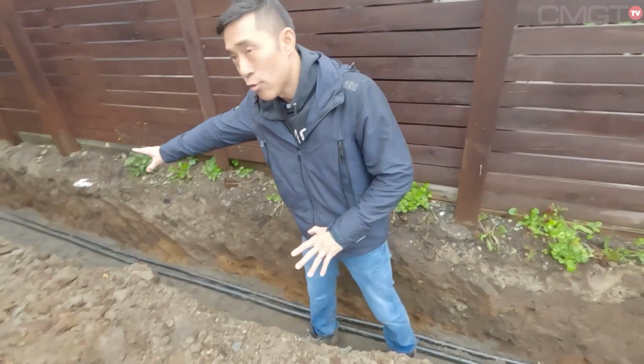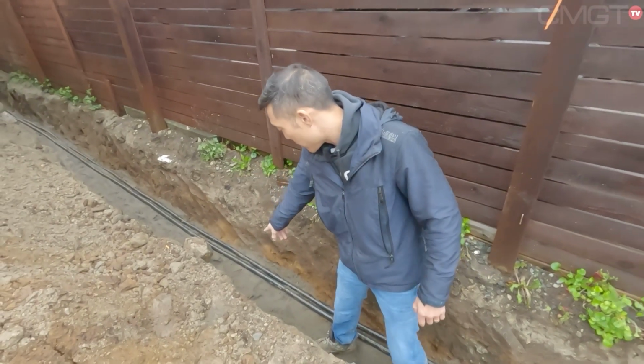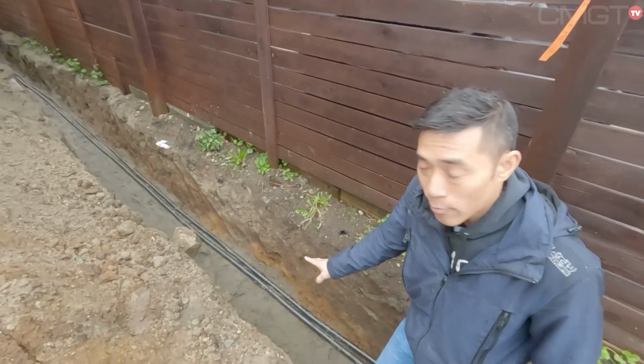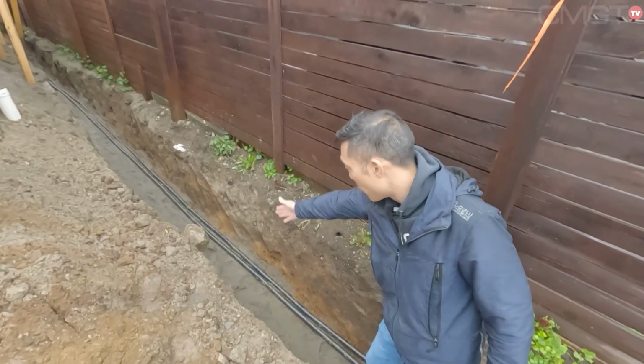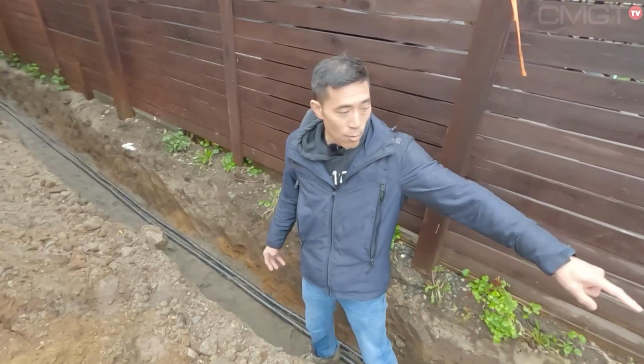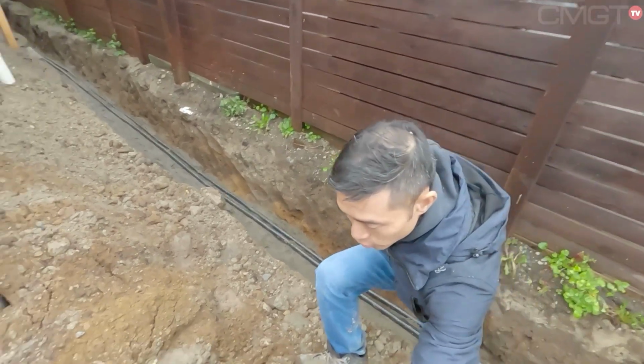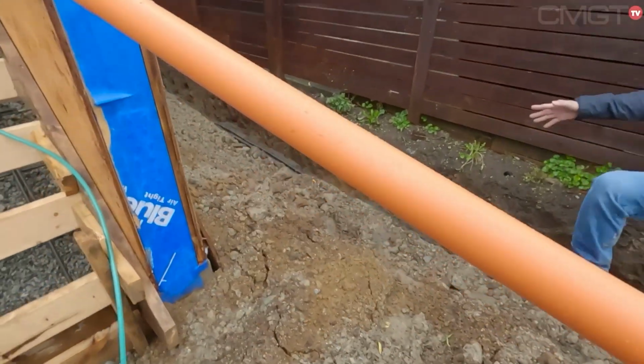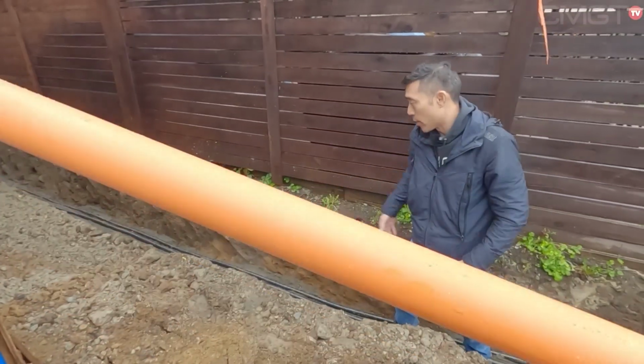Where I'm standing here in the trench, there's 6 inches of sand on the bottom. This is mandatory when it comes to inspections. The two Teck cables running from the house to the garage, and this right here, this 2-inch DB2, will rest inside this trench as well before it gets backfilled.